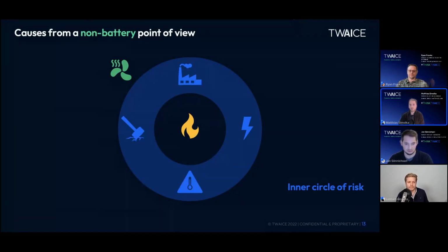Another example from the news: other components in the system next to the battery started creating smoke, which triggered a sprinkler system - which is the benefit, or what was planned, it performed as it was supposed to. But of course, with batteries and water, that just doesn't work too well. You ended up creating a short circuit with the battery cells, and then went into thermal runaway, and you know the story then.